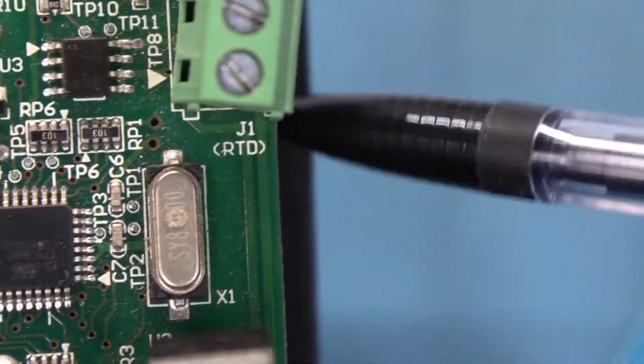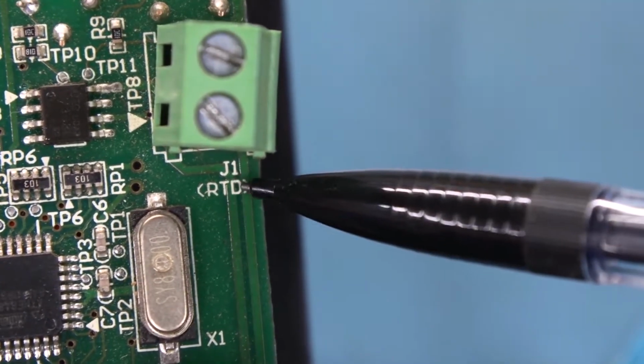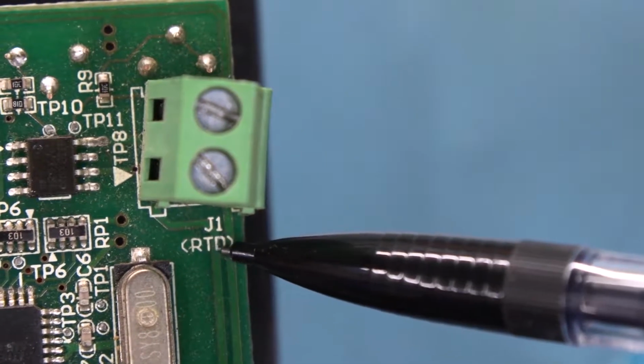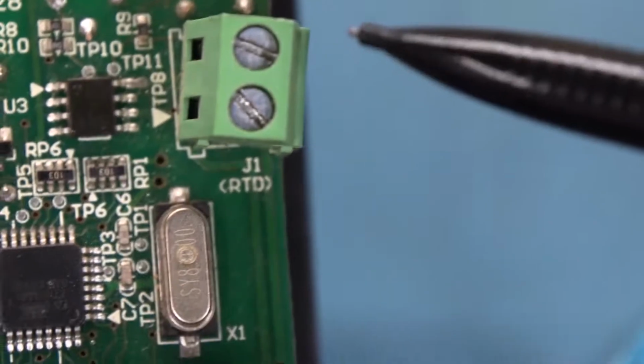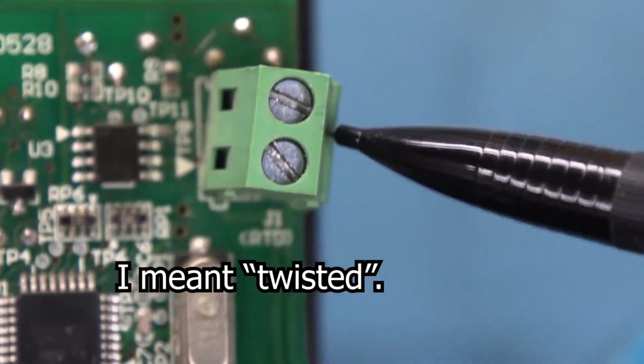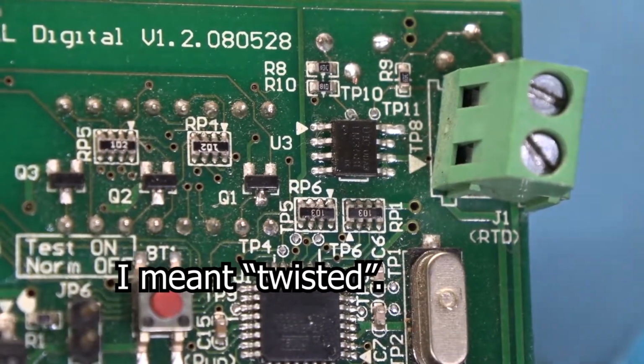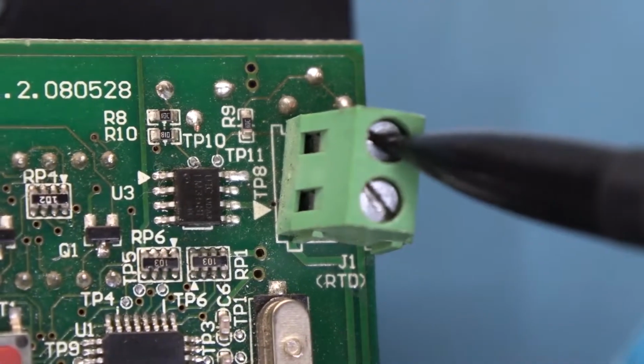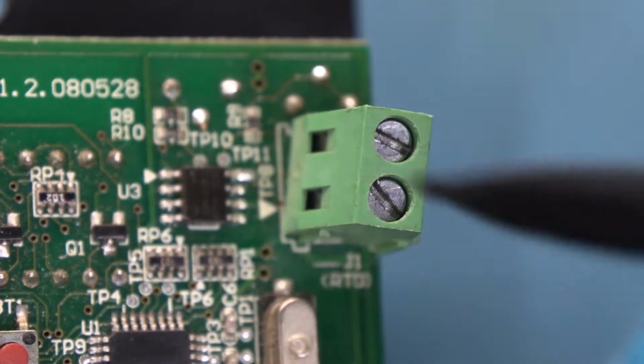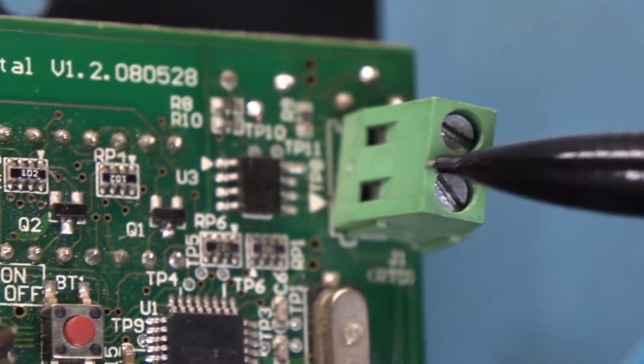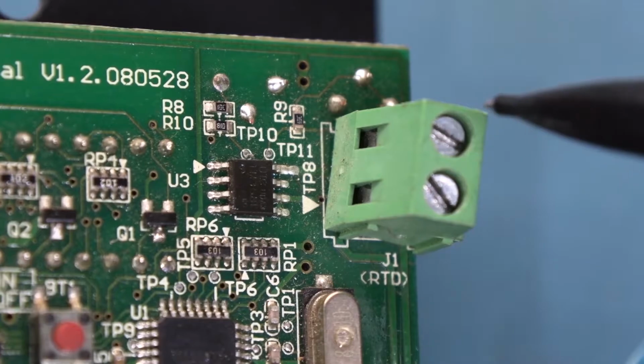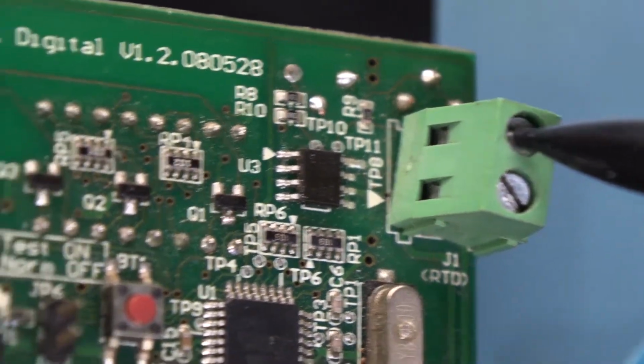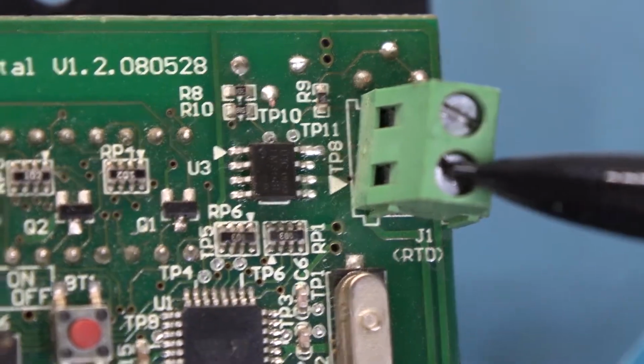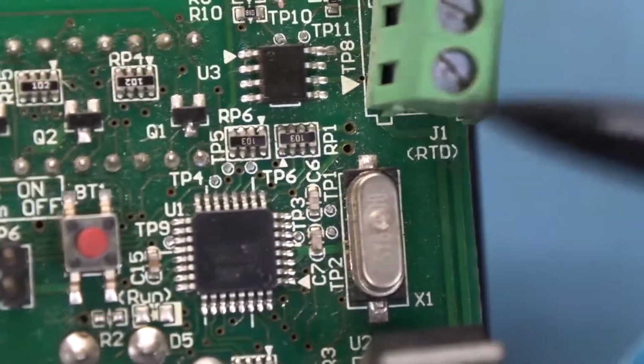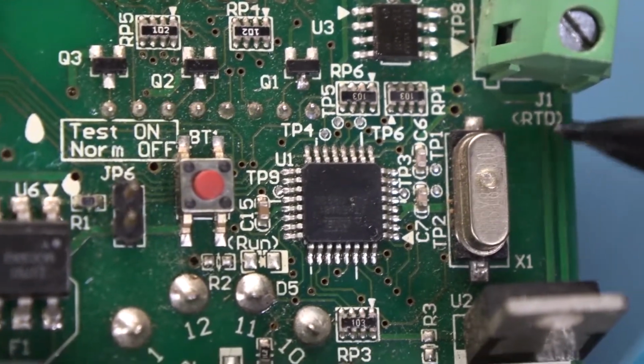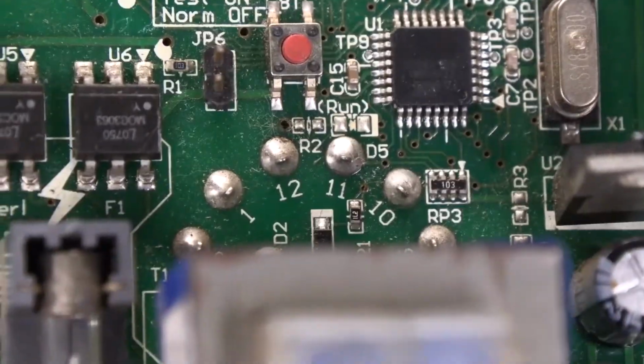Okay, here's where you connect the RTD temperature chamber probe. It's a PT-1000, and I wanted to show you how it's bent on the board. That's because when you tighten these screws up right here, you tend to tweak that, and it turns this 2-post terminal block - it's going to twist it off eventually. So yeah, that needs some better binding posts on there, probably something with mounting holes on the bottom to keep it from twisting like that.